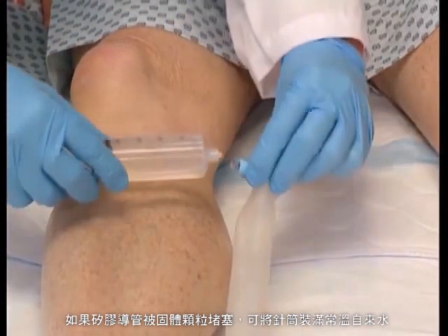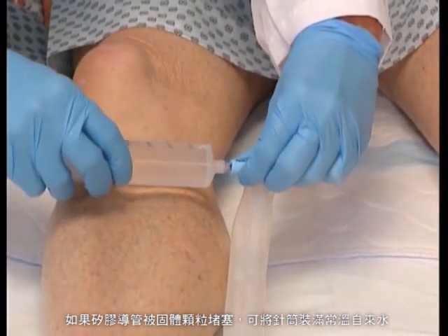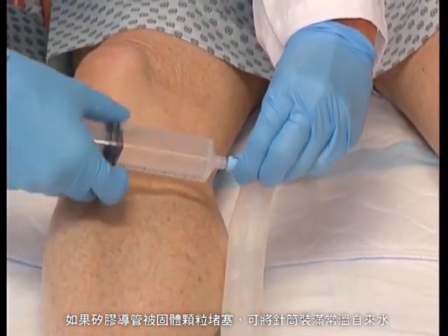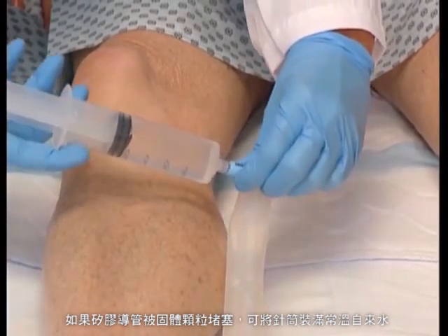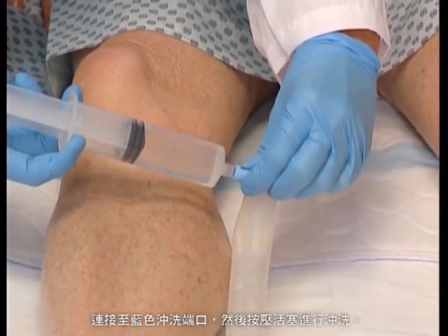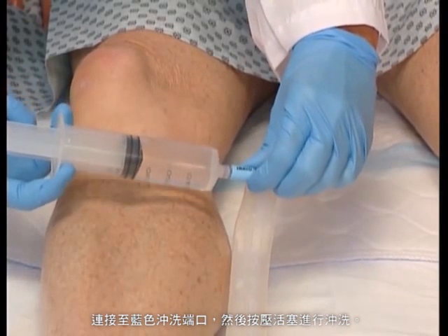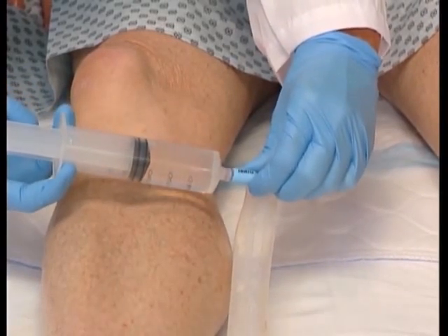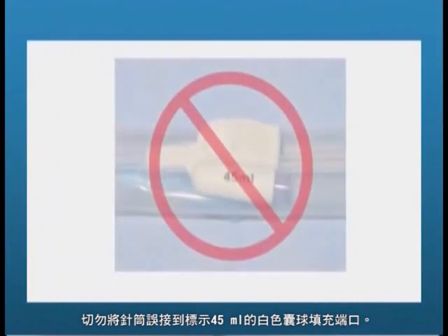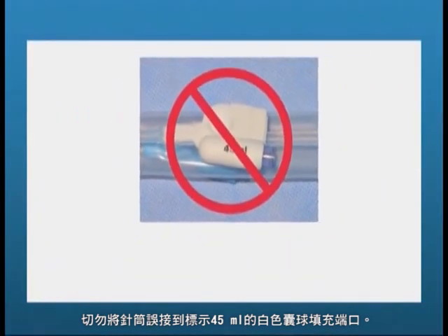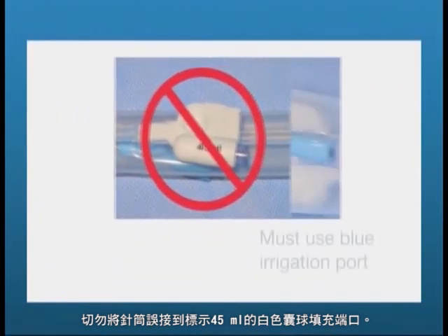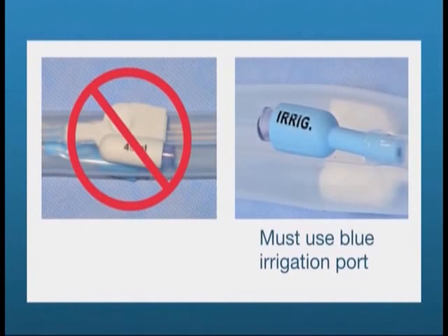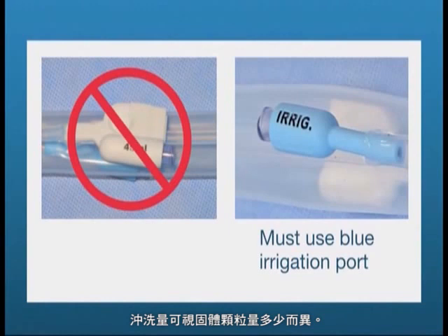If the silicone catheter becomes blocked with solid particles, it can be rinsed by filling the syringe with room temperature tap water, attaching the syringe to the blue irrigation port, and depressing the plunger. Ensure the syringe is not inadvertently attached to the white balloon inflation port marked 45 ml. Irrigation amounts may vary depending on the amount of solid particles.